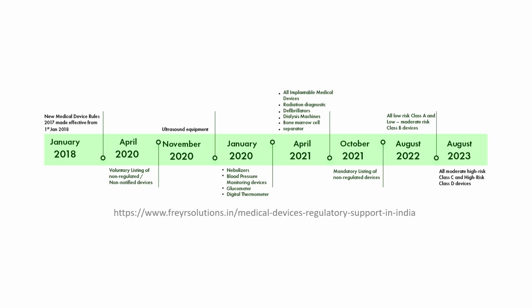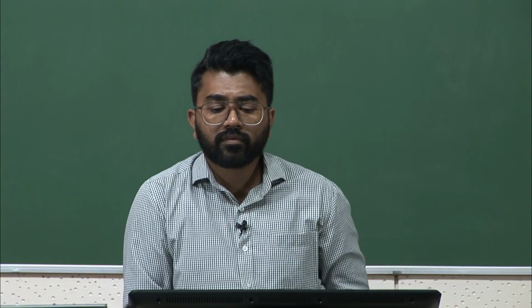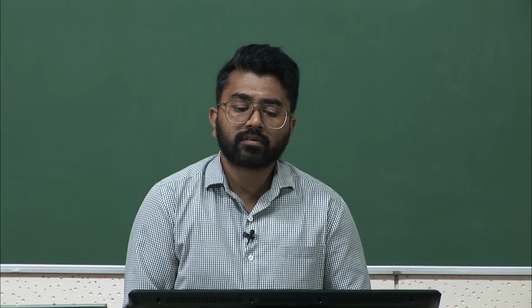April 2021, all implantable medical devices were placed under regulations. Before this, many of these implantable devices did not have regulations properly. Now, all the implantable devices, be it a dental implant or a hip implant or a stent implant, whatever implant you are looking at, any invasive implant device within the body is coming under regulatory compliances, right, and they are categorized under the different medical device risk categories.